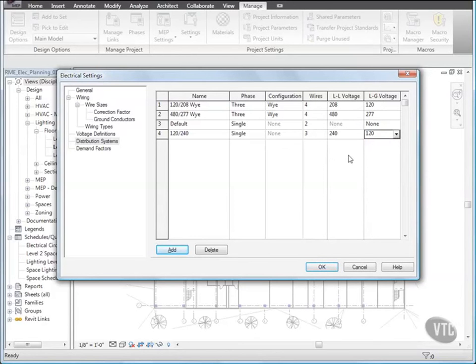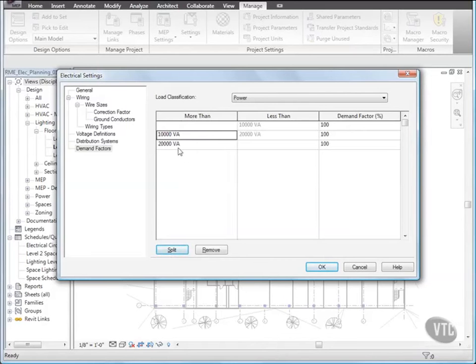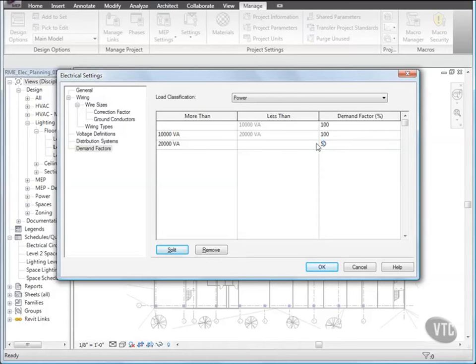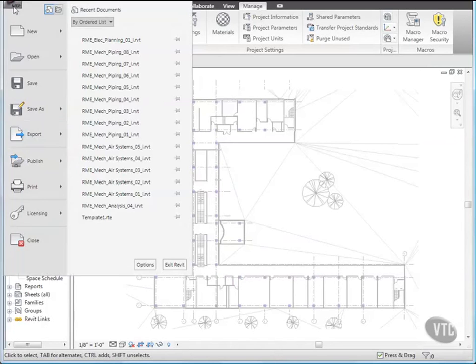Next, we'll specify Demand Factors. Select Demand Factors, and for Load Classification, select Power, and under More Than, select 10,000 VA, and then click Split, and select 20,000 VA, and for Demand Factors, enter 50. Click OK, and close the file without saving it, as the next lesson will provide its own training file.